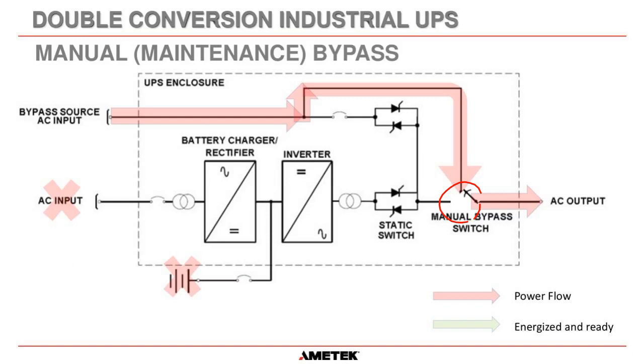You can see the contact has changed here, and that means power will now flow around here, down, and out that way. That means if your AC input is off and your batteries are disconnected, there is going to be no power going to the rectifier bridge itself and the inverter bridge itself.